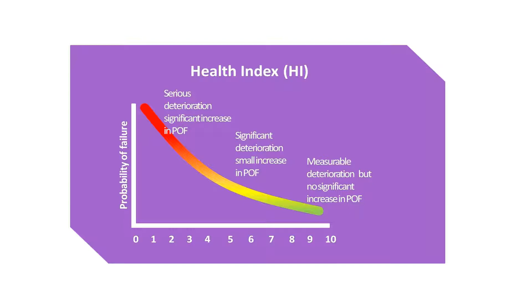So this is about health index, and health index defines the probability of failure. If it's 10, the probability of failure is very low - your transformer is not going to fail. But if you're in this zone, the probability of failure is very high and your transformer is going to fail. So based on health index, the probability of failure is derived mathematically using a formula. Health index is the base, from which you derive the probability of failure.